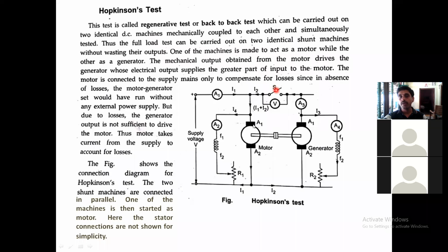Starting point is: switch is open, excitation of the motor is adjusted to rated speed, excitation of generator is adjusted to get the voltmeter reading 0, then the switch is closed, then this generator is in parallel to the supply. So this is the beginning condition. At this condition, we will take the readings of motor field current, generator field current, as well as the line current. That's what is explained in this slide.